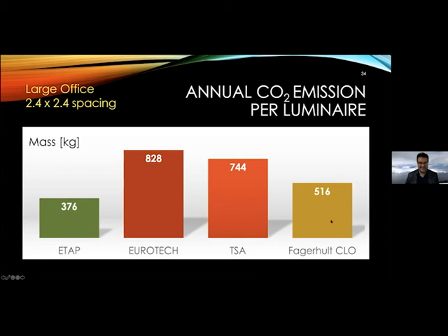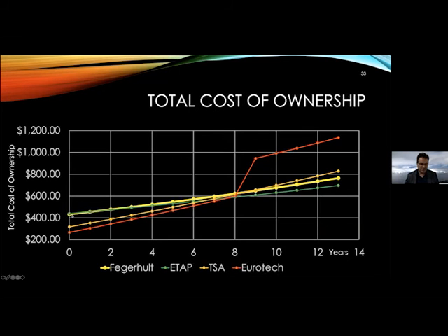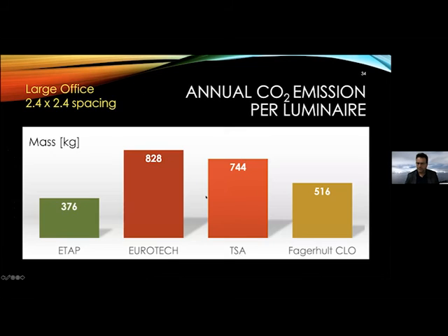This is the Fagerhult CLO drive. This is the very driver that I spent some time talking about, which got intentionally reduced power when the luminaire is brand new, and gradually power is being increased. So this is that particular one, Fagerhult. Okay, so you have to be aware. The longer you use this product, the more and more power is being consumed by these drivers.